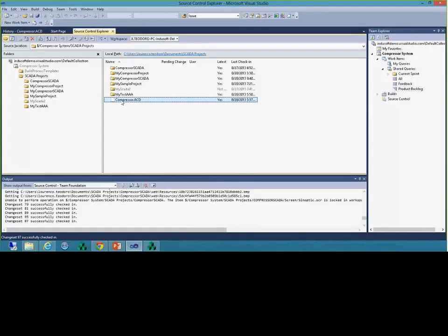If you have that, you're going to have a very hard time collaborating. Plus, they don't have full integration. So you have to come to the TFS Explorer, perform the checkouts on your files, and use the TFS Explorer to check in. When you're using InduSoft Web Studio, because we save all the configurations on different files, it makes it a lot easier to have different users working on different things at the same time. Also, you can perform the checkout and check-in on InduSoft because we have everything fully integrated.